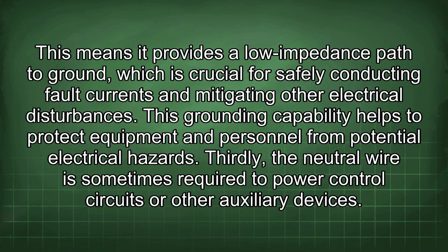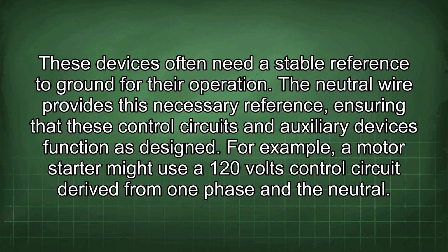Thirdly, the neutral wire is sometimes required to power control circuits or other auxiliary devices. These devices often need a stable reference to ground for their operation. The neutral wire provides this necessary reference, ensuring that these control circuits and auxiliary devices function as designed. For example, a motor starter might use a 120 volts control circuit derived from one phase and the neutral.